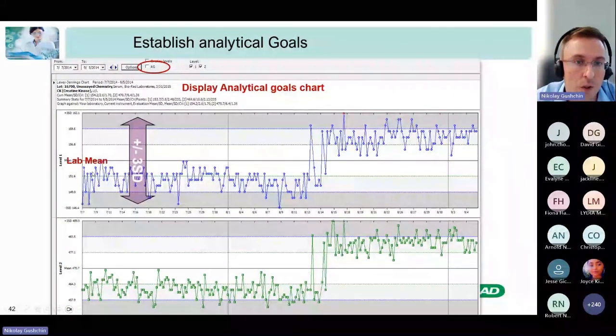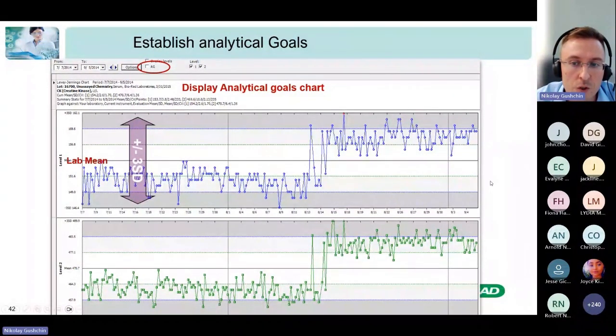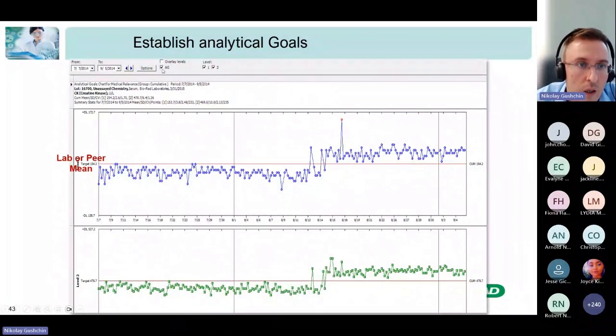This is the regular Levey-Jennings chart, your regular statistics, so lab mean plus or minus 3 standard deviations. And when you click this AG checkbox, which means analytical goals, now we have another limit on this chart, which is target plus or minus the total allowable error. And we can see the same data, but with other allowable limits.